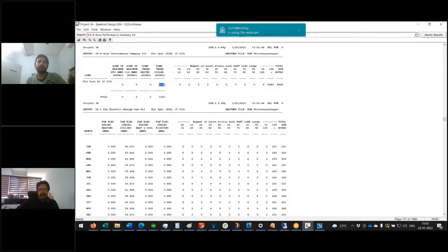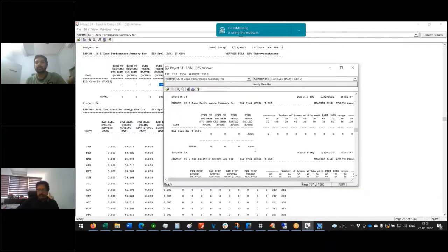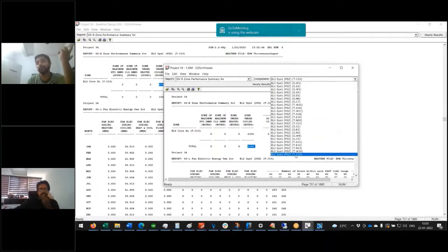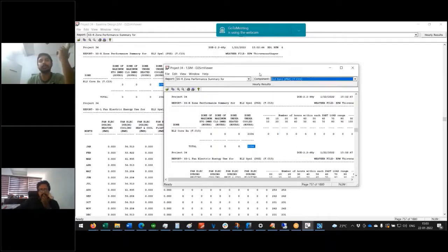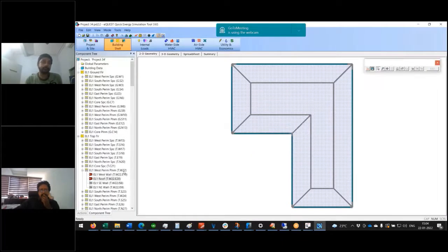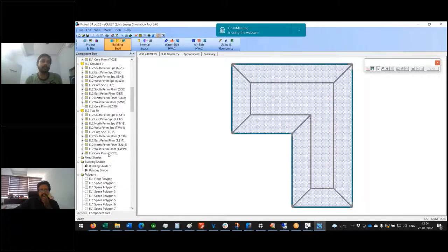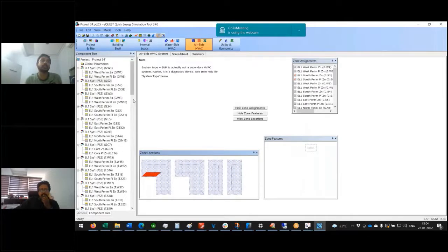So 2361, and now it is coming to 2336. Okay, so that means there are other things which are happening, and one of the main things is, as I said, there's pent up heat. The amount of heat that is being stored is insufficient. So the best way is to actually increase the cooling capacity or the flow rates, and it would automatically result in a higher cooling capacity, right?